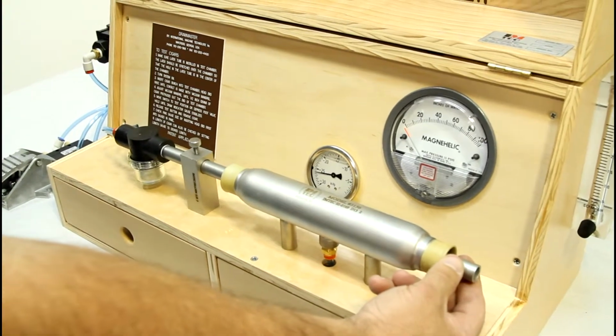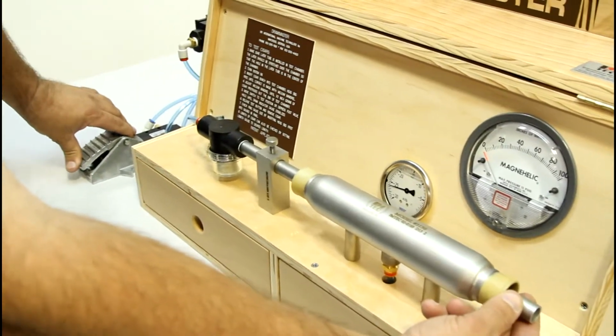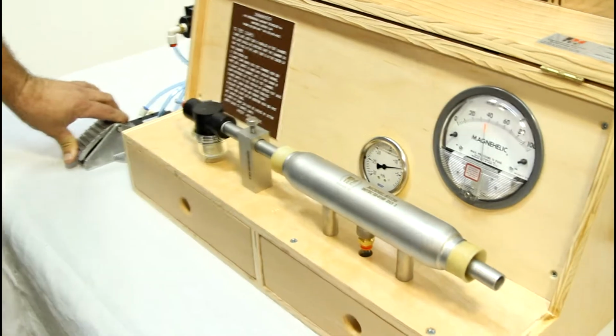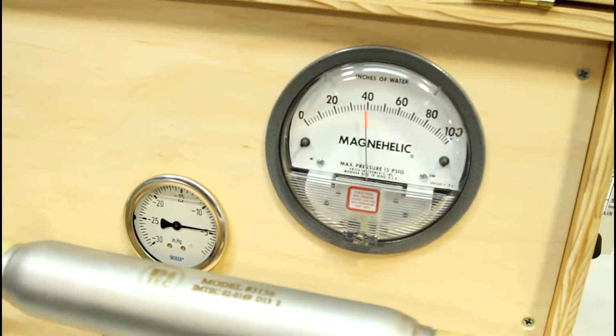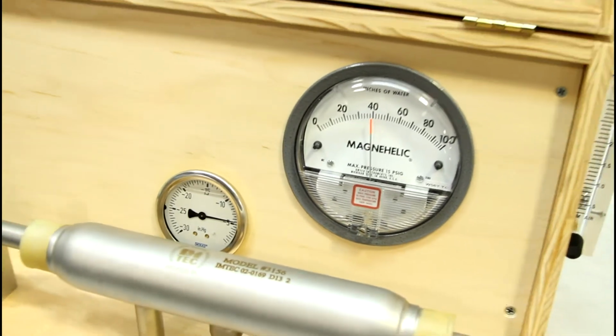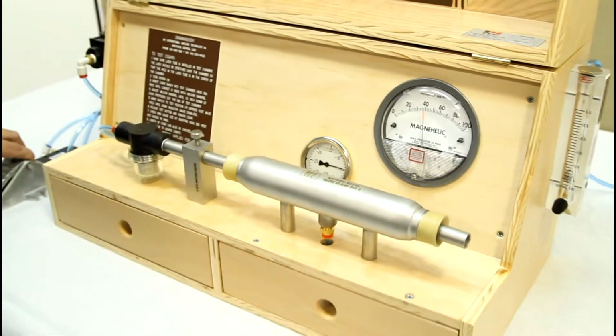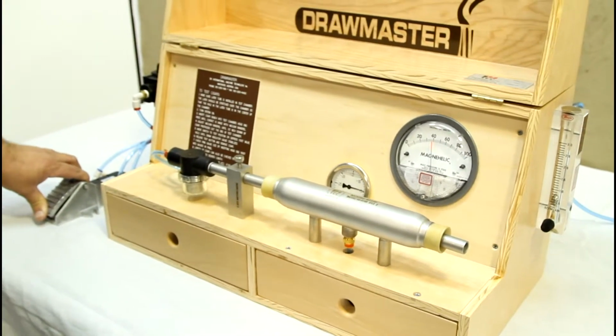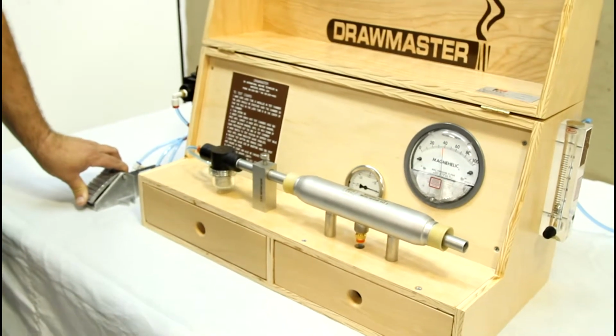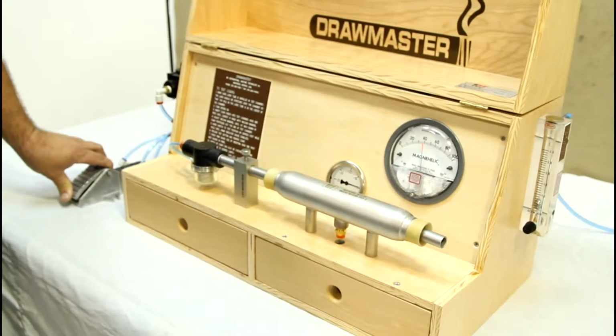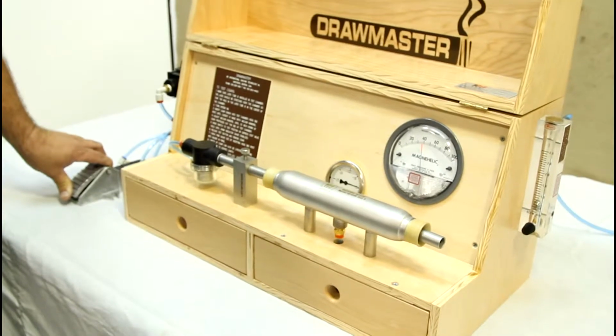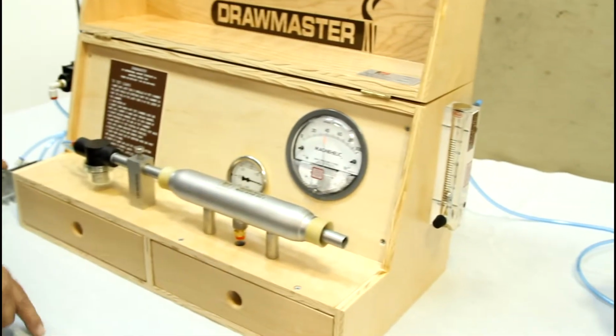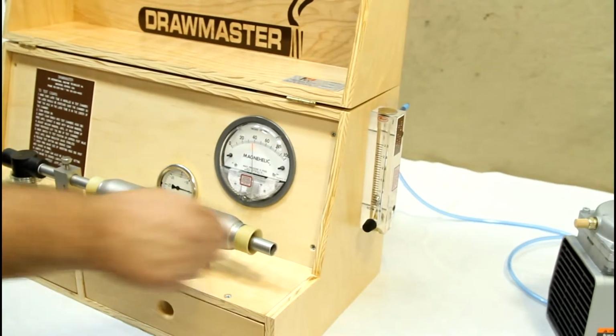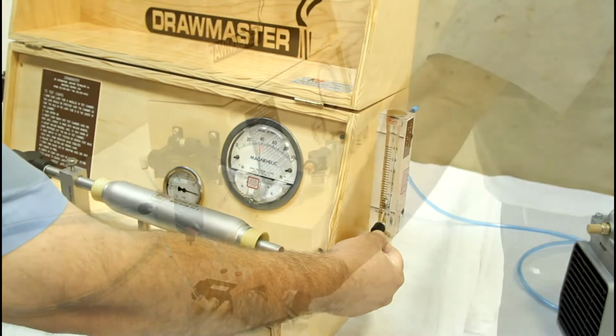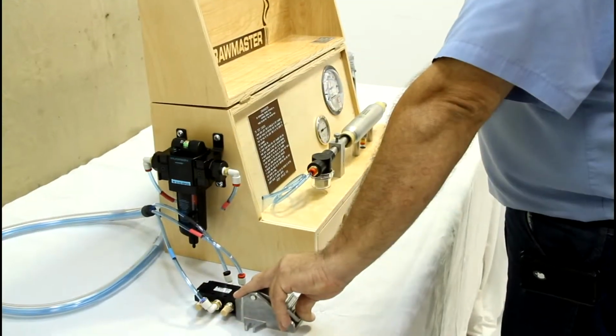You now depress the foot valve to the test position. The magnehelic gauge should read number 40. If the machine does not read 40, you bring the machine into proper calibration by adjusting the small black knob at the bottom of the flow meter until the gauge reads 40. Now release the foot valve.